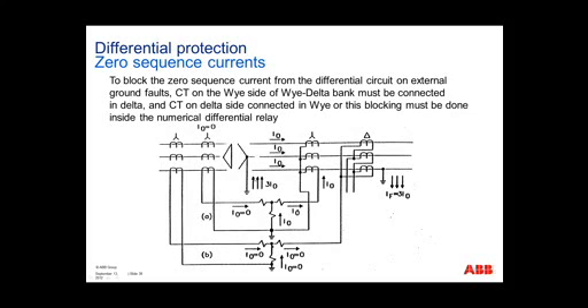However, on the Y side, since we do have a ground connection and we have a Y connected CT, we have a source of zero sequence currents, and the relay will detect these zero sequence currents, causing the relay to misoperate. If we connected the CTs into Delta on the Y side, we can see that there will be no zero sequence currents circulating going to the relay. So your net zero sequence currents will stay zero, hence not tripping.